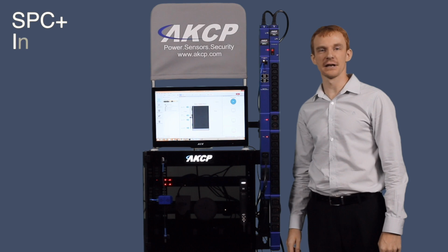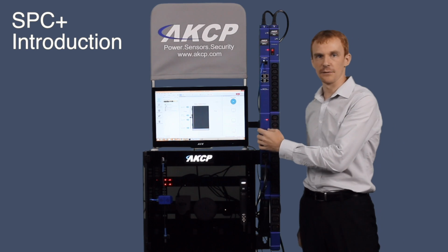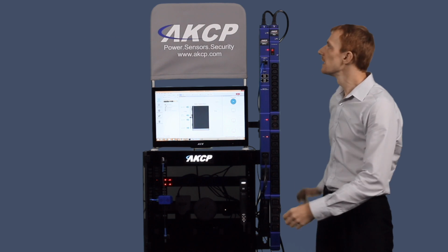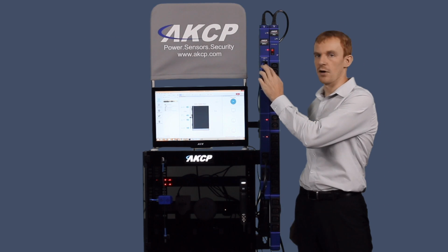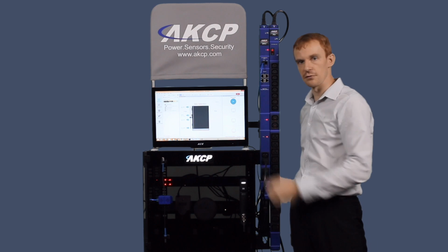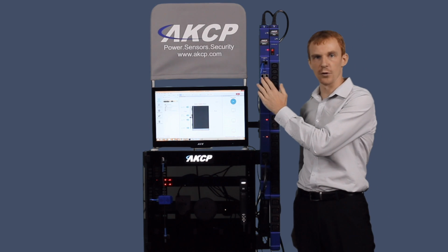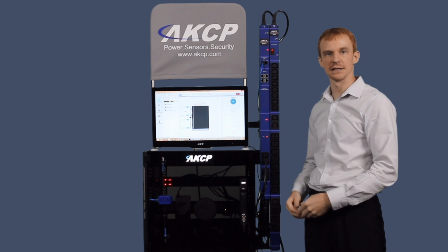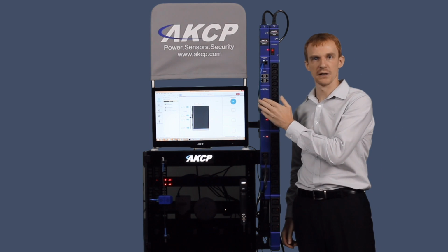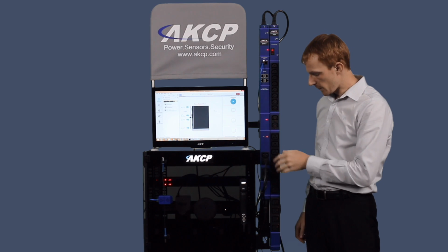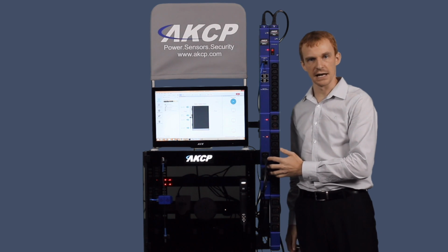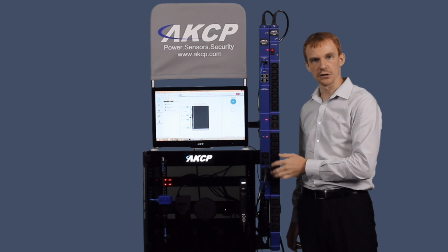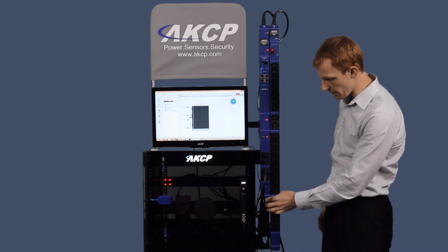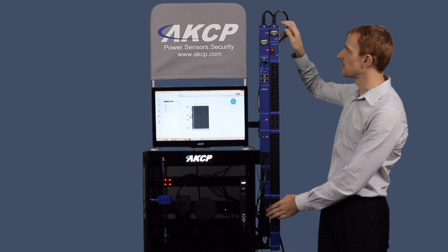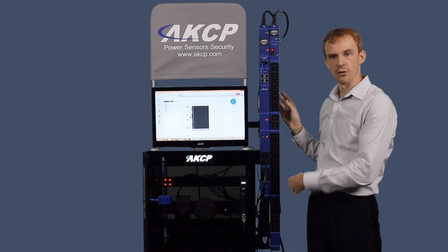So let's take a closer look at the units we have on display here. On the left side, I've got mounted our SPC Plus remote device. At the top we have the power coming in. We have our basic expansion bus connected back to our 1U gateway mounted inside the cabinet. We have 4 additional sensor ports for connecting any of AKCP's intelligent sensors. We have our power meter and power relay, followed by 4 additional C13 outlets, which are switched with 2 relays on a 2x2 basis. Finally, we have the power coming out at the bottom, which connects to the power in of your existing power strip, or in this case, our AKCP PS Plus.